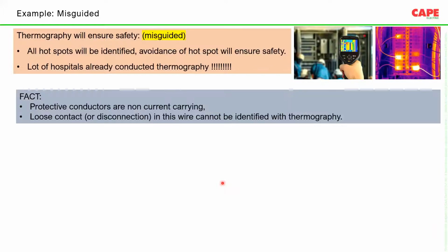In a hospital or in a general location, safety is ensured by the protective conductor. The protective conductor is not a current carrying conductor. It is always in an off condition. There is no current flowing, and you cannot find out the integrity of the protective conductor by doing thermography. So the purpose of thermography is beaten at the first step itself.